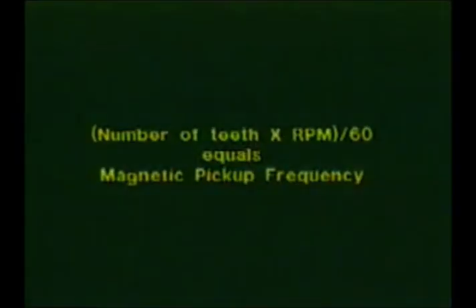And what you need to do is, we're running off a mag pickup. You need to know the number of teeth that are on the gear that you're having the mag pickup hooked to. You take the number of teeth times the speed of the engine, in this case it's 1800 RPM, and then divide that by 60, and that will tell you the frequency your engine will run at.